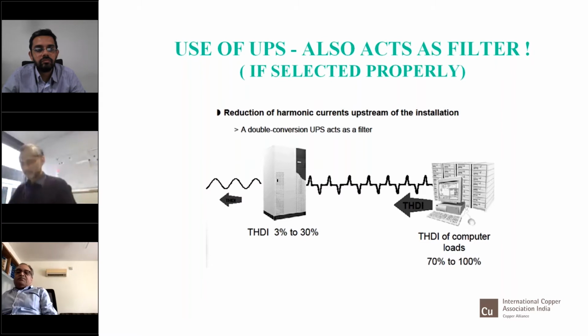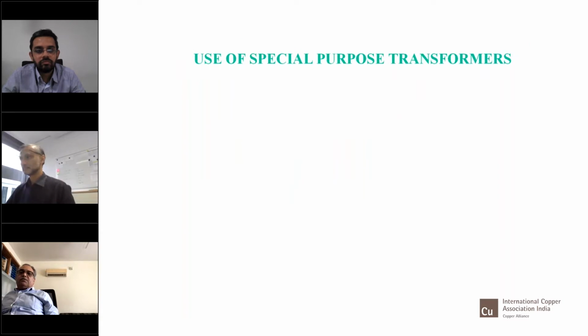and the transformer would still get heated, because international law says, or even Indian law now says, that the harmonics that you inject into the grid should not be more than 5%, and you would be penalized, and the transformer will get heated. So you have to be very careful while selecting your UPS.